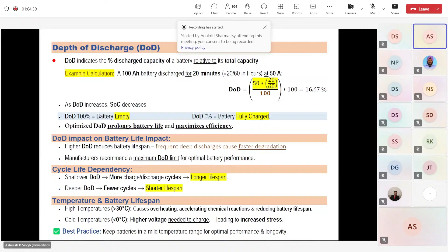Then comes another term I was talking about, cycle life, and how this cycle life is related with DOD is also shown in this diagram. Cycle life refers to the number of charge-discharge cycles a battery can sustain throughout its useful life before its capacity significantly degrades. This degradation in battery life depends on two points: depth of discharge, and operating conditions, meaning temperature, charging, discharging, and how this depth of discharge is compensated with the charging phenomena.